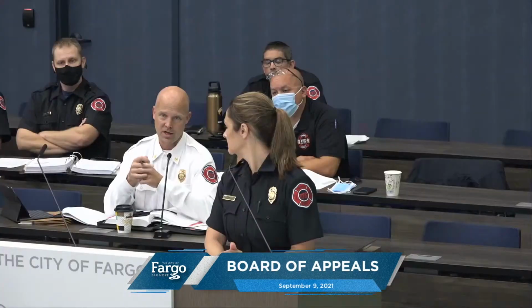Special amusement areas are very restrictive in that sense. So if you, let's say you wanted to put in a puzzle room and you wanted to lock them in, you will be required to sprinkler it. So you'll have to be in a building that has a sprinkler in it, or you'll have to bring a sprinkler in for that. Yep, or, so the other thing we've seen though is there's actually other ways to do it.